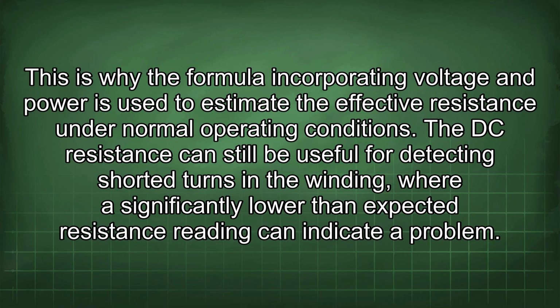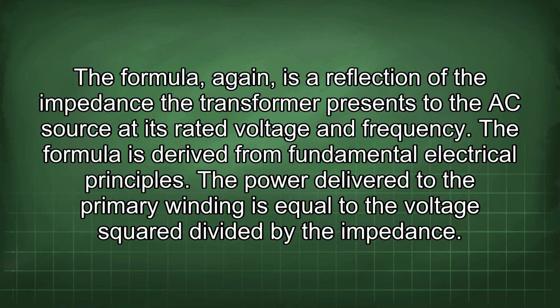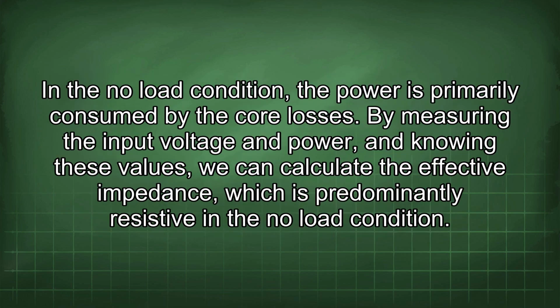The DC resistance can still be useful for detecting shorted turns in a winding, where a significantly lower than expected resistance reading can indicate a problem. The formula, again, is a reflection of the impedance the transformer presents to the AC source at its rated voltage and frequency. The formula is derived from fundamental electrical principles. The power delivered to the primary winding is equal to the voltage squared divided by the impedance. In the no-load condition, the power is primarily consumed by the core losses. By measuring the input voltage and power, and knowing these values, we can calculate the effective impedance, which is predominantly resistive in the no-load condition.